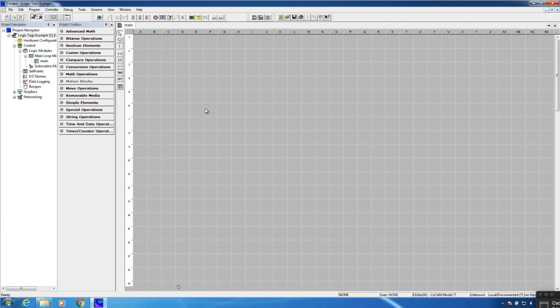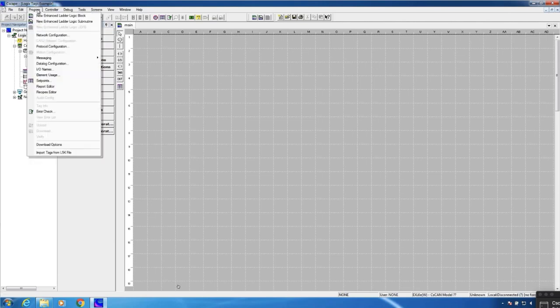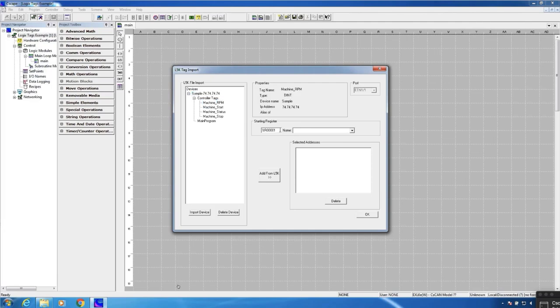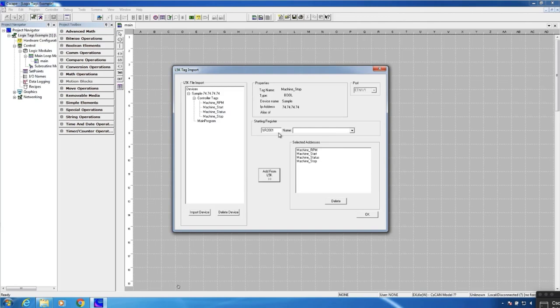To take that extra step, go back into the program menu and back to 'Import Tags from L5K File.' We don't have to re-import anything — we've already done that. What we do need to do is map over the tags we're interested in. Let's say we wanted to map all four tags. I also need to assign a starting register where those can be mapped in OCS register space. Let's put them at register 2001. We'll start with machine RPM, hit Add; move to machine start, Add; machine status, Add; machine stop, Add. We've now added all of those, mapped into OCS register space starting at register 2001.